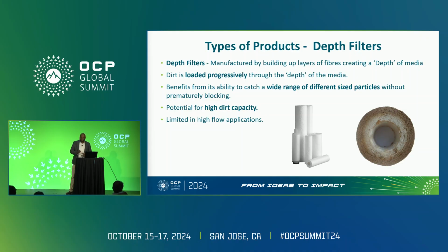I would like to give a glimpse of the filter media products that you would typically rely on to protect the liquid cooling systems and are taking over the exhibition floor space. They're all over the place. The main product is the depth filter. This is a very versatile piece of kit. It performs quite well in a wide range of different applications. It can remove quite a wide range of particles, whether it's a gel, colloid, or hard particles, due to the nature of the media. It has what we call a graded density and a tortuous pathway, which makes it quite versatile.